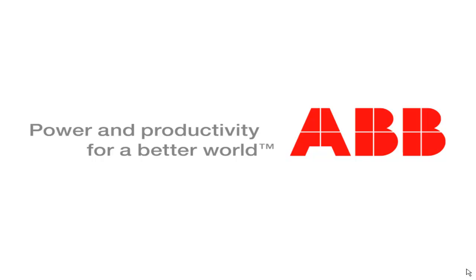Derek Thompson from La Hoist. On your first one, your phosphate removal, would you adjust the pH with a liquid lime to remove the phosphate as a solid calcium phosphate? We normally don't need to do much pH adjustment on the phosphorus removal, because with our normal electrocoagulation, we find the alkalinity level rises naturally anyway, and we just incorporate that into the system. So no, we don't normally add any liquor such as base into the systems for phosphorus removal.